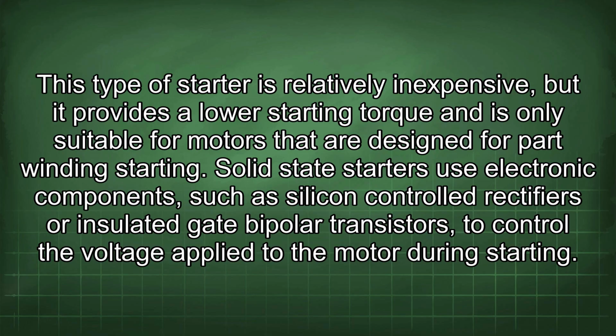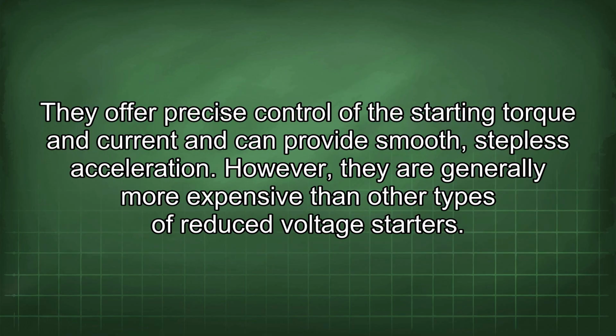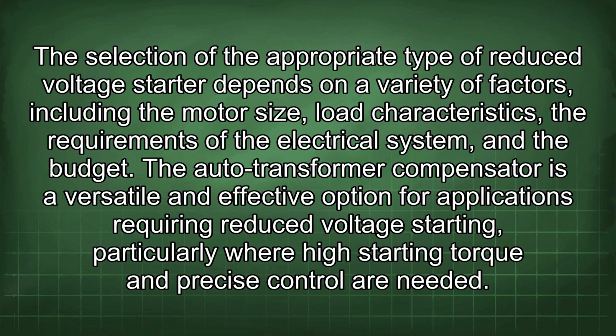Solid-state starters use electronic components such as silicon-controlled rectifiers or insulated gate bipolar transistors to control the voltage applied to the motor during starting. They offer precise control of the starting torque and current and can provide smooth, stepless acceleration. However, they are generally more expensive than other types of reduced voltage starters. The selection of the appropriate type of reduced voltage starter depends on a variety of factors, including the motor size, load characteristics, the requirements of the electrical system, and the budget.